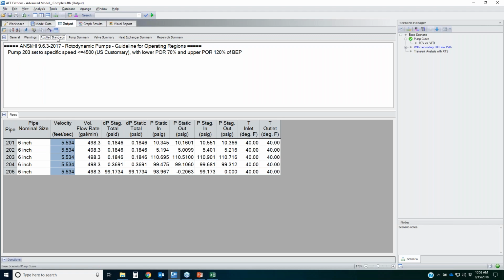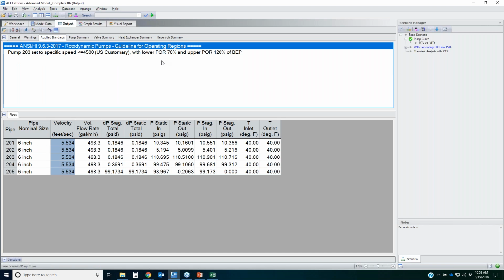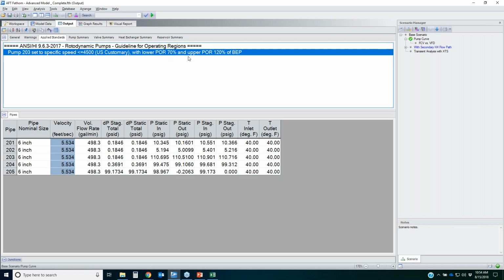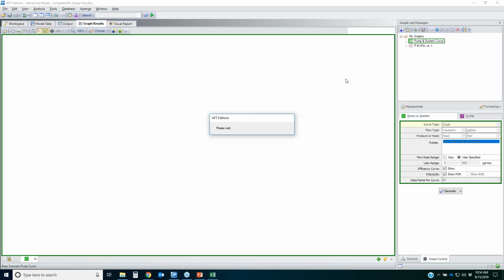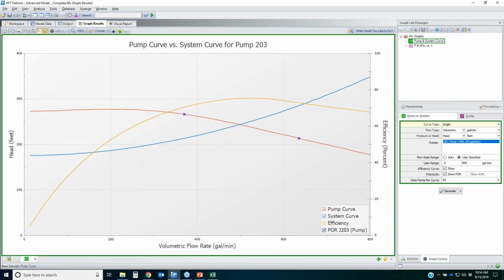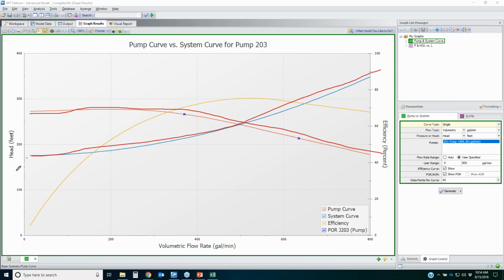If we look at the applied standards, that's where our preferred operating range comes from. So I'm using the Hydraulic Institute standard for my preferred operating range, which has to keep my pump operating between 70 and 120% of the BEP. I then went to my graph results tab, and I have a pre-developed pump and system curve. So if I plot this right here, I've got several things on the graph. I've got my red curve, which is just my regular pump curve. The blue curve represents my system curve. So I've got my static head component, and then I have my friction component right here. Okay, that's the frictional component of the system.